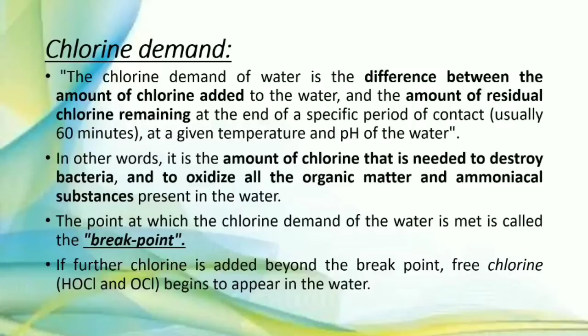The point at which the chlorine demand of water is fulfilled is called the break point. If we add further beyond the break point, free chlorine begins to appear in water. That is superchlorination. Contact period: there should be a contact period of at least 1 hour, which is essential to kill the bacteria and viruses. The minimum recommended concentration of free chlorine is 0.5 mg per liter for 1 hour. And the sum of chlorine demand plus free residual chlorine is the correct dose of chlorine to be applied to the water. Both constitute the correct dose of chlorine to be applied.